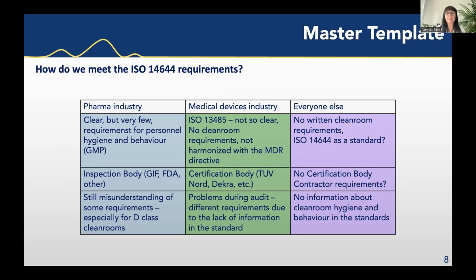What about the other industries? So in the medical device industry, where you have ISO 13485, it is not so clear because there is no information that you need a clean room to produce medical devices, even if you produce sterile ones, or you sterilize your medical devices, you sterilize your products. So the main problem, I think, is that ISO 14644 and ISO 17141 still aren't harmonized with the MDR directive. So it means that on the list of standards, there is no information that you should confirm the requirements of the clean room standards.